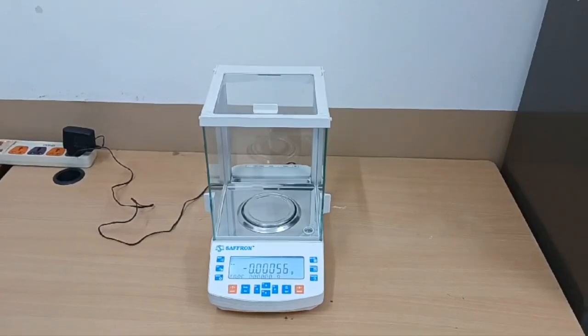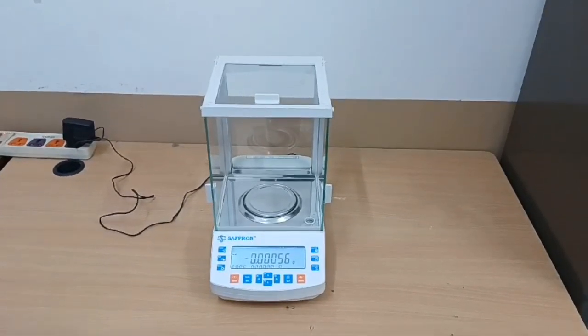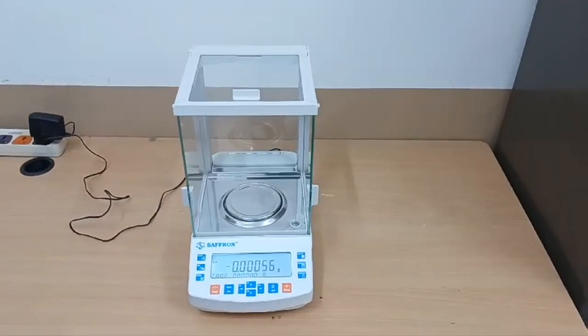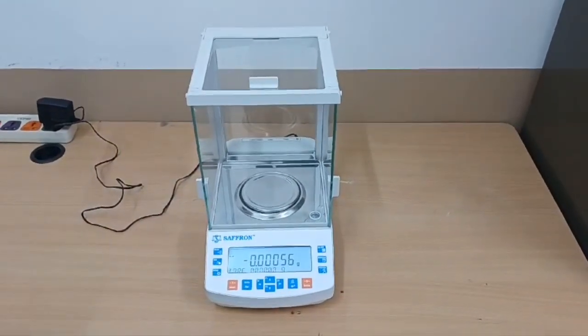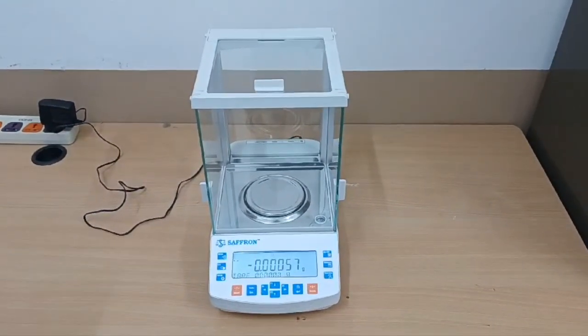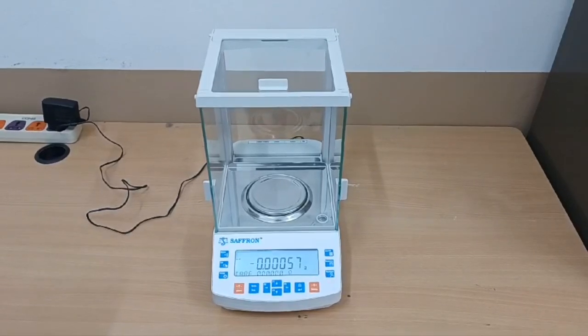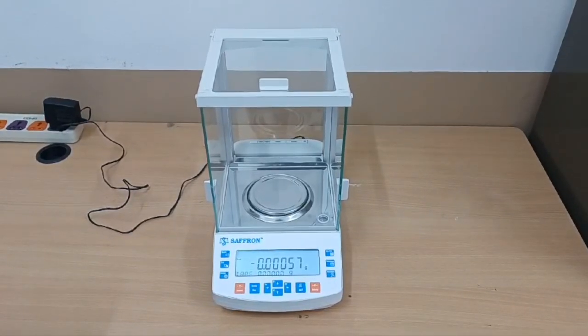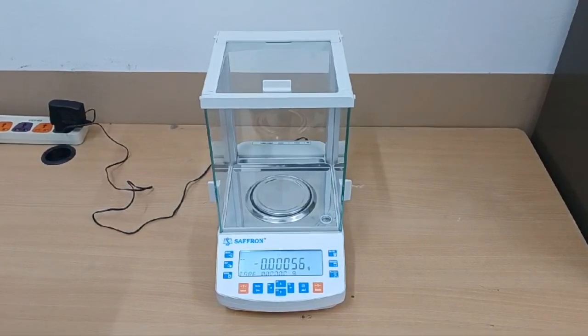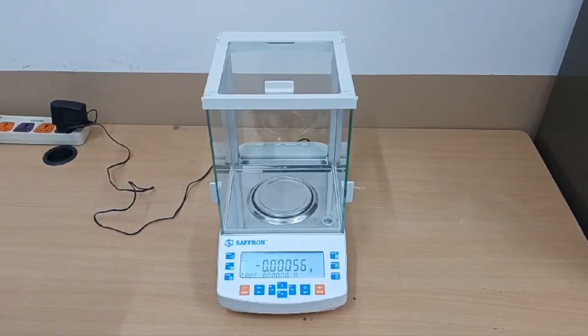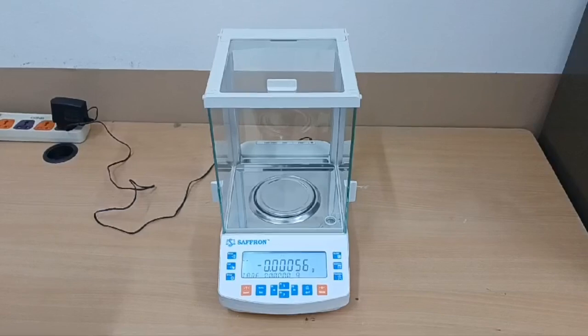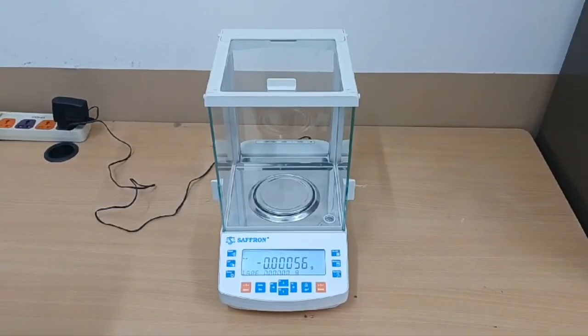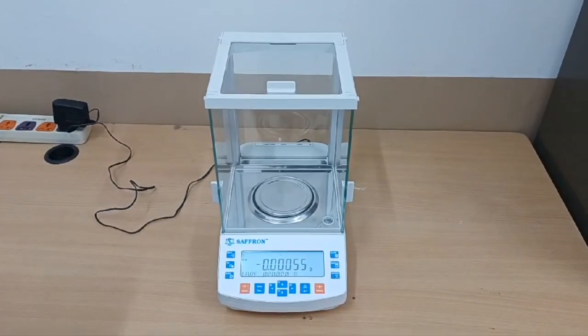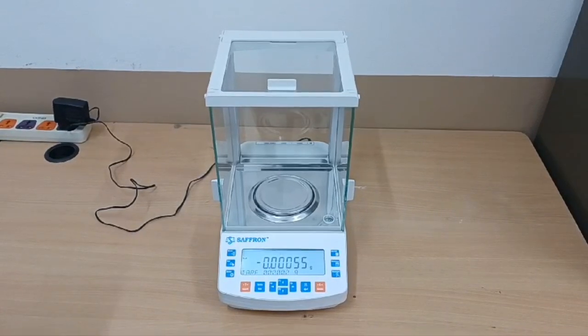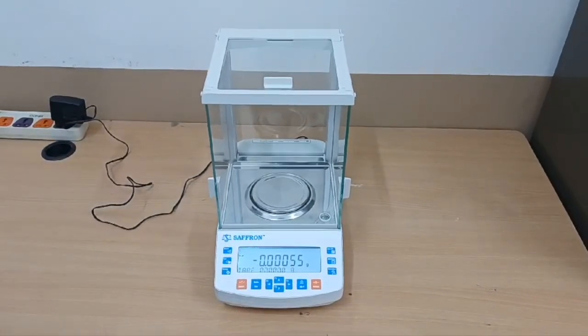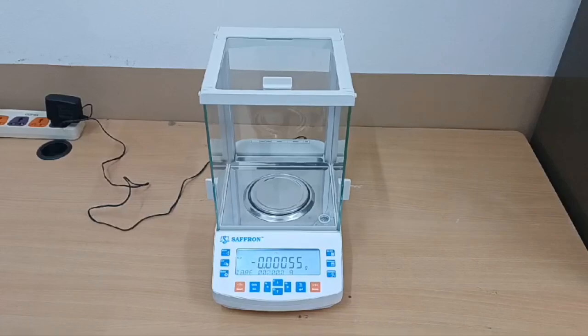So I'm going to list out a few of the inappropriate uses that we should be aware of. Basically, it should not be used as a dynamic weighing instrument. Even if small quantities of weighed material are added or removed, the reading should only be taken after stabilization. No magnetic materials should be placed on the weighing pan, as this can cause damage to the measuring system of the instrument. The third one is to avoid any impact shock or overloading. Basically, any weight that's placed on the pan should be placed there carefully.